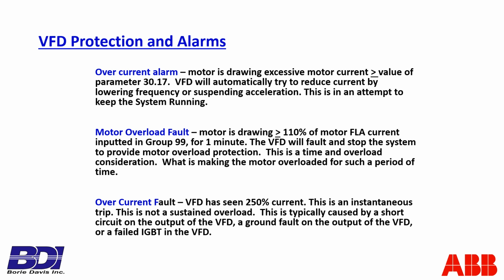Well, typically what might cause it to occur would be that we're trying to accelerate too fast. The voltage and frequency signal is sent to the stator of the motor, and it creates a magnetic field, and the rotor tries to follow it. If the load on the rotor is so big, a large inertia, that what we're telling it to do by coming up in a certain time period is more than it can handle, it's going to draw more current to try and make that happen. That might cause this overcurrent alarm.